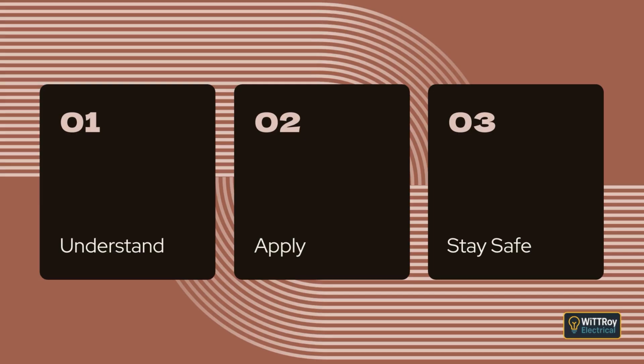Protection is required wherever maintenance staff may be exposed to mechanical hazards while working on the equipment, or where the equipment may need to be stopped quickly in an emergency to remove danger. The standard requires that there must be a means to disconnect or isolate the equipment so that maintenance and emergency stopping can be carried out safely. In simple terms, if something moves, there must be a safe way to shut it down.